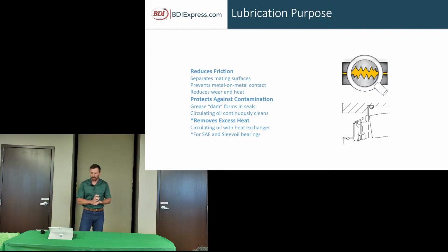So bearing lubrication is there to reduce friction. If you look at an inner ring or an outer ring of a bearing race, you're going to see little peaks and valleys, but what that lubrication does, it creates a coat around there, so those rolling elements or ball bearings, which are typically used in air handling units, are going to be protected by that film over that. If you didn't have any lubrication, that's going to cause heat with metal wear. That's going to reduce your bearing life. And it also protects against contamination, forms a dam.